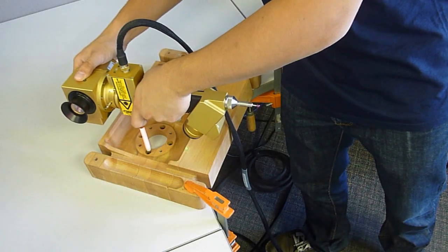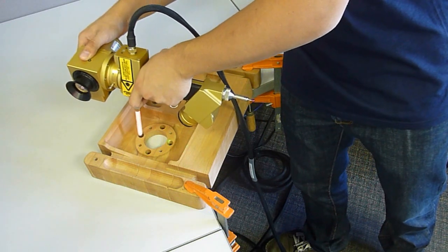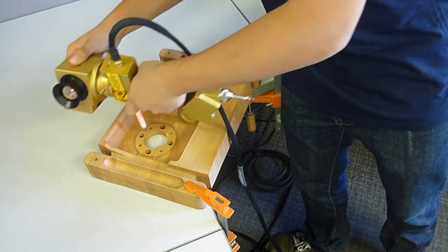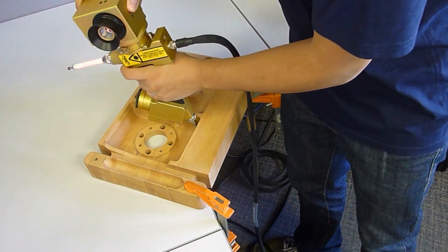The iProbe can be used with the vertical or the horizontal stem. The stem lengths available are 5cm and 10cm. They allow you to probe corners or holes that a normal SMR cannot.